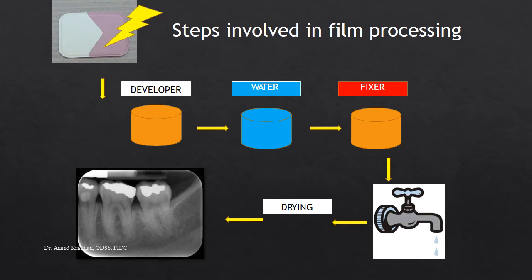The steps for manual processing are common to both methods: you go into the darkroom, open the packet, remove the film, put it in developer, then water, then fixer, then rinse it in running water, and dry it off. The order is the same, but how we approach it differs between the time-temperature and visual methods.